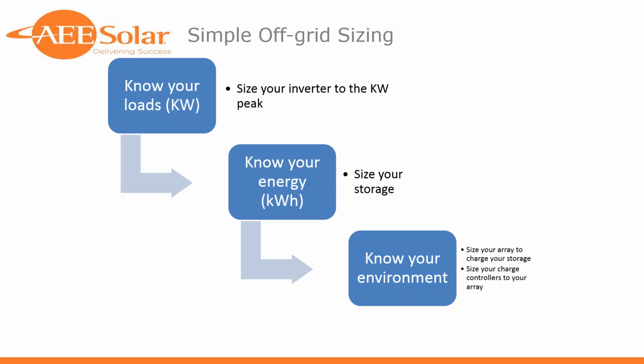What's the 95th percentile number for what your kW is going to be if all the loads are on at once? I say 95th percentile because I think it can be debilitating to think about a scenario where every single appliance or light is turned on in the customer's location. Use your best sense of what they're going to run concurrently. That's going to give you your kW number.